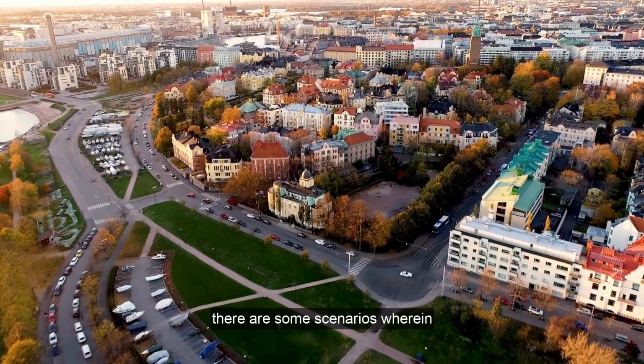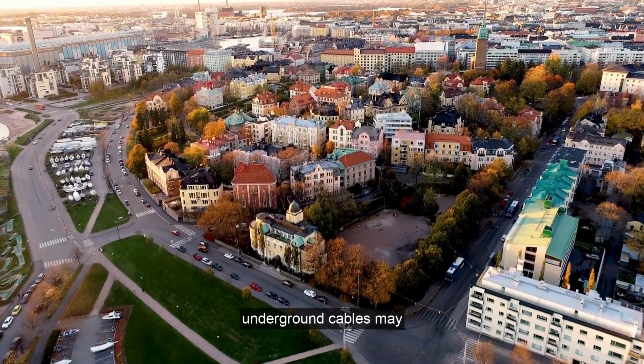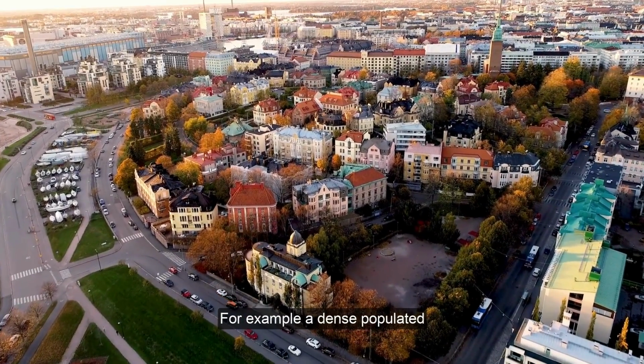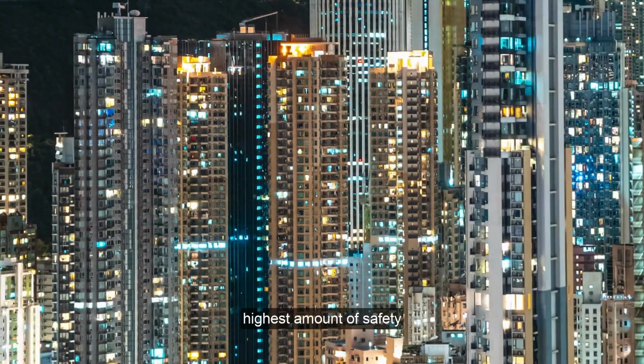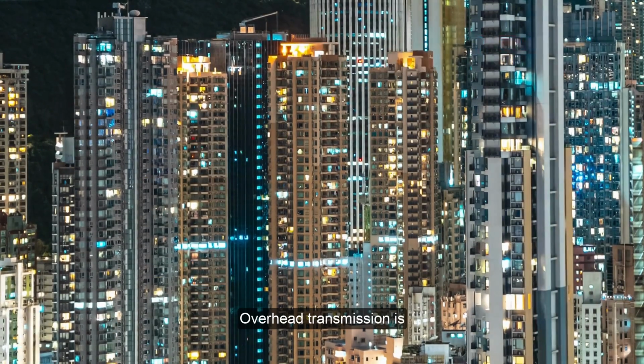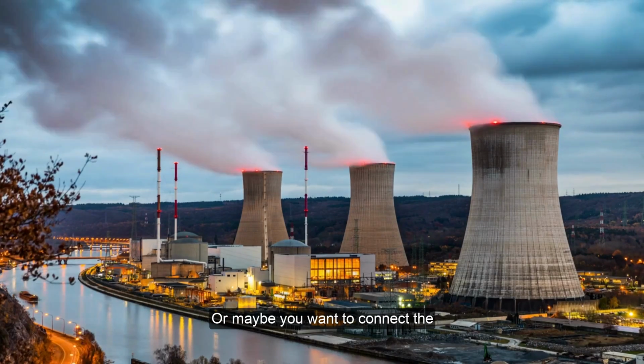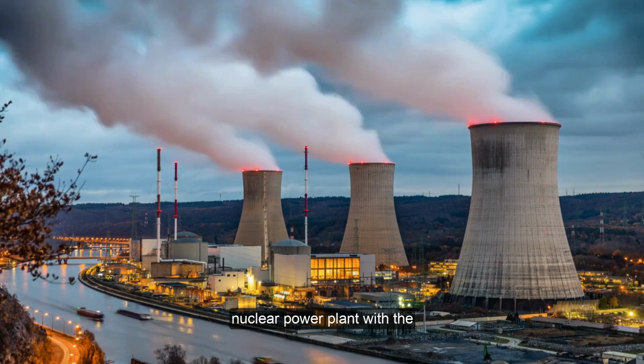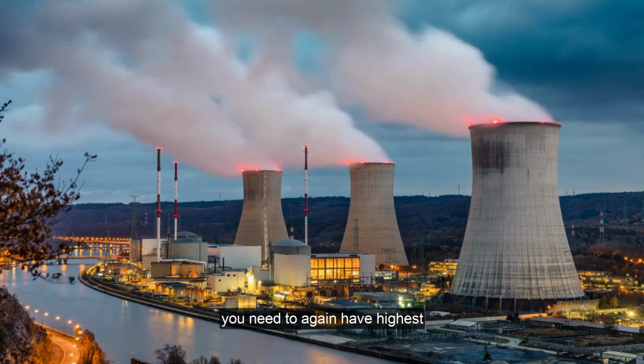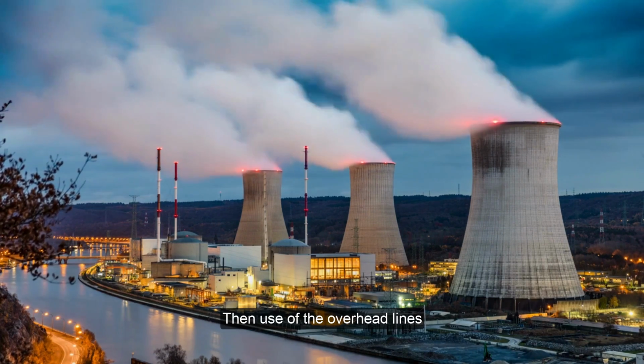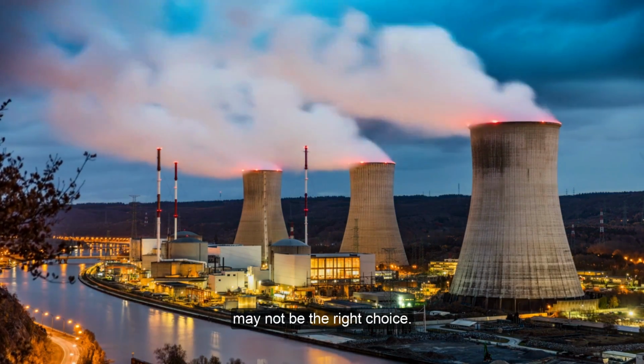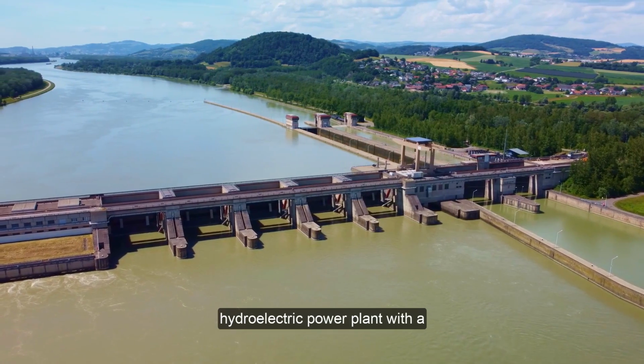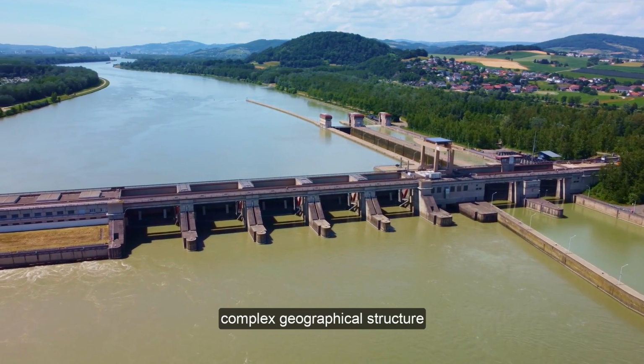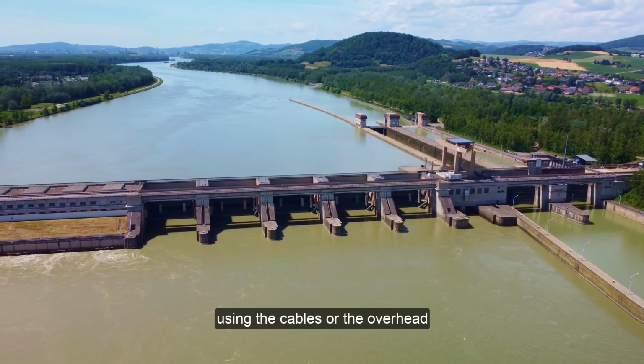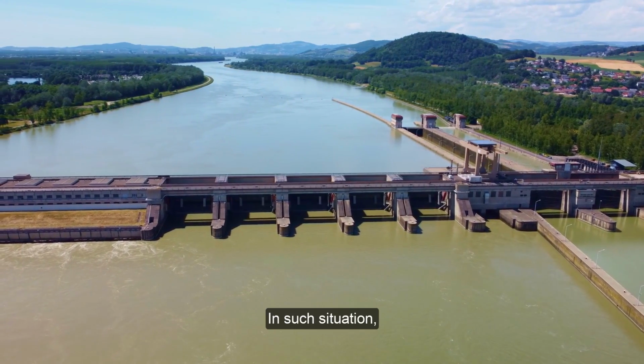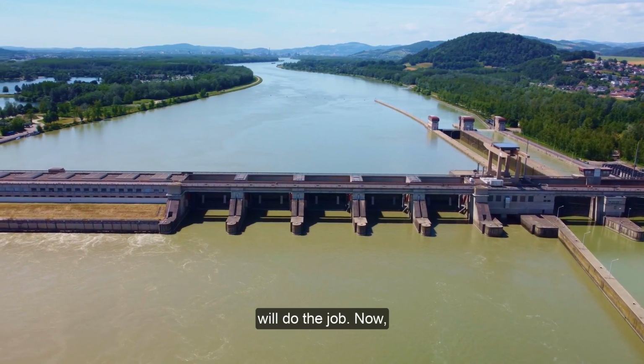Now there are some scenarios wherein the use of overhead lines or underground cables may not be possible. For example, in a densely populated city where you need the highest amount of safety, overhead transmission is not the right solution. Or maybe you want to connect a nuclear power plant with the transmission network, where again you need the highest amount of personal safety. Or maybe you have a hydroelectric power plant with a complex geographical structure, where cables or overhead lines are not feasible. In such situations, gas insulated lines will do the job.